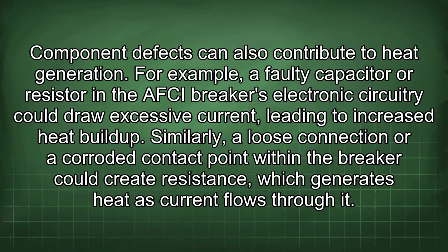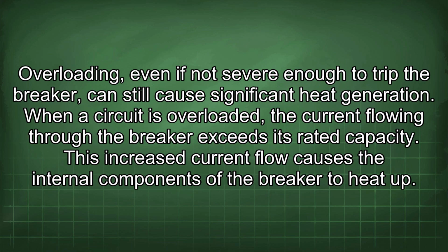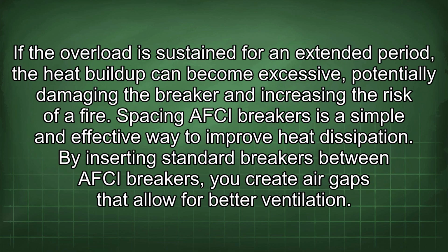Overloading, even if not severe enough to trip the breaker, can still cause significant heat generation. When a circuit is overloaded, the current flowing through the breaker exceeds its rated capacity. This increased current flow causes the internal components of the breaker to heat up. If the overload is sustained for an extended period, the heat buildup can become excessive, potentially damaging the breaker and increasing the risk of a fire.